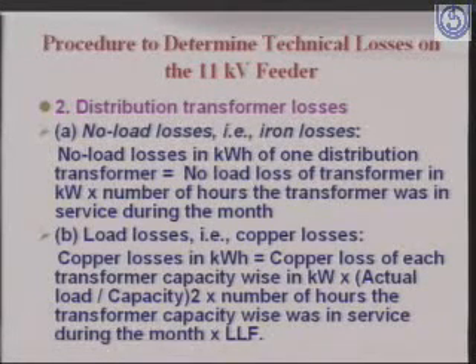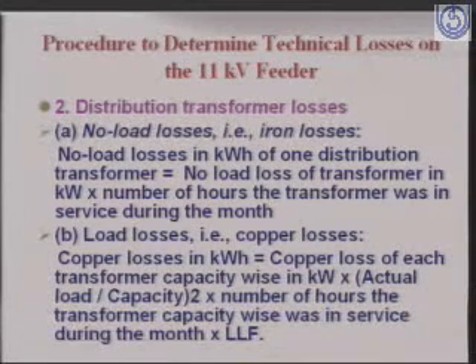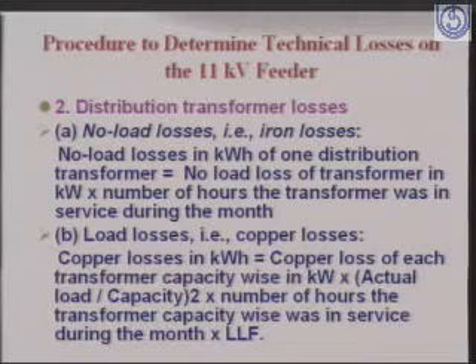Load losses: the load factor we calculated, and then the loss load factor, is used here. The copper loss is also mentioned on the nameplate rating of the transformer. Then the actual load by the capacity of the transformer, squared, and the number of hours, into the loss load factor. This is what is mentioned in your book. This is the correct method. But if you want to avoid this method, as I said, what our engineers in the manufacturing facilities do is work out the average load on the transformer divided by the capacity of the transformer, squared, multiplied by the copper loss. That gives you the load loss of the transformer.